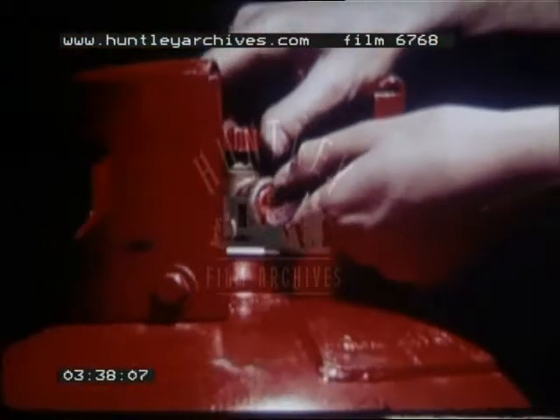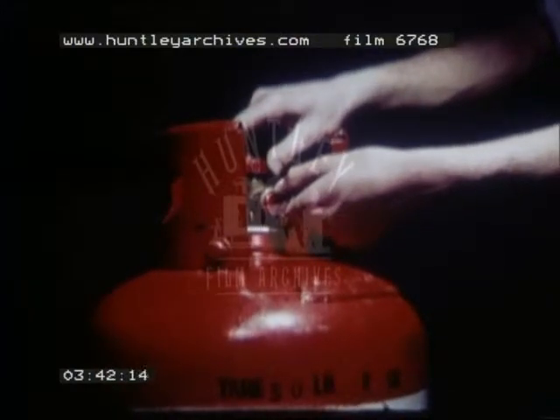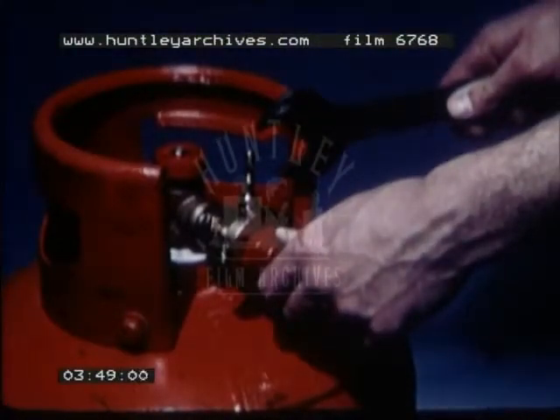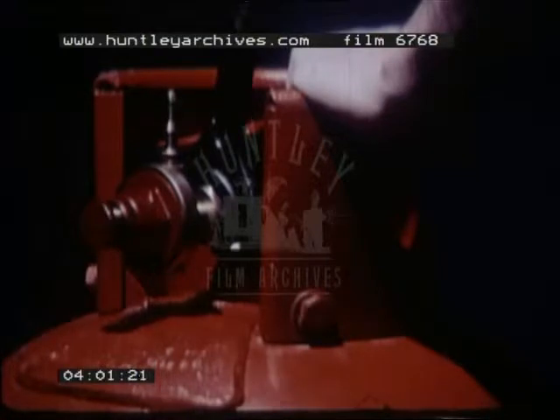Before removing the plastic plug, make sure that the valve on the cylinder is closed. It may have shaken loose or been accidentally turned on during transit. When connecting up the pressure regulator and pipework from the appliance, always have the appropriate spanner ready. Having screwed up the nut by hand, tighten all connections with the spanner. Remember, it is a left-hand thread.